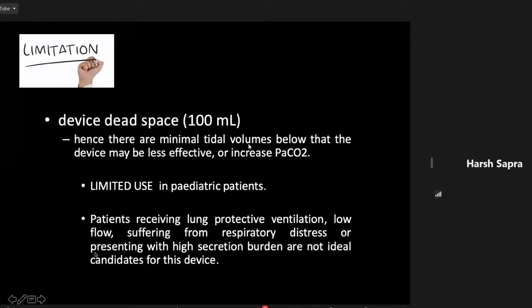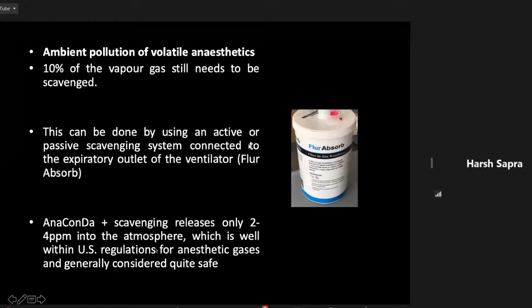So ambient pollution, obviously 10% of the vapor gas still needs to be scavenged. This is done by the Flur Absorb, and Anaconda plus scavenging releases only 2 to 4 ppm into the atmosphere, which is well within the US regulations for anesthetic gas and generally considered quite safe.